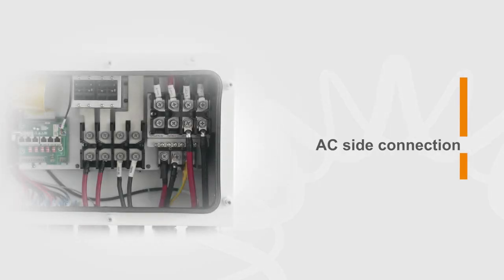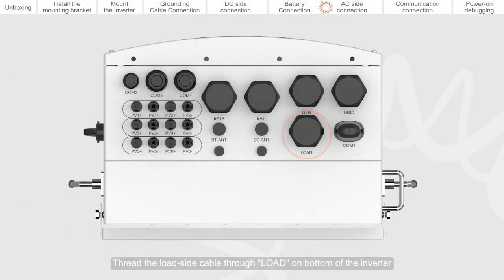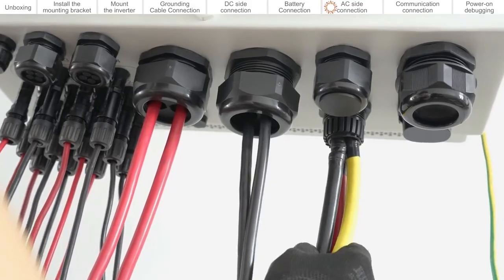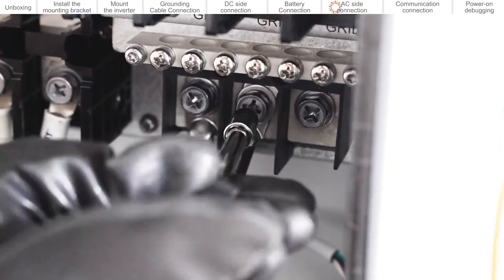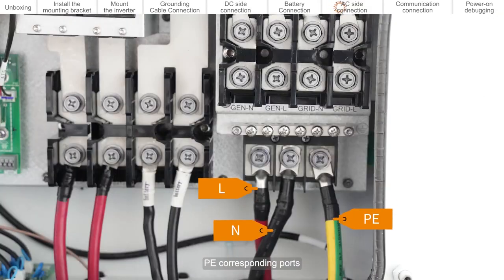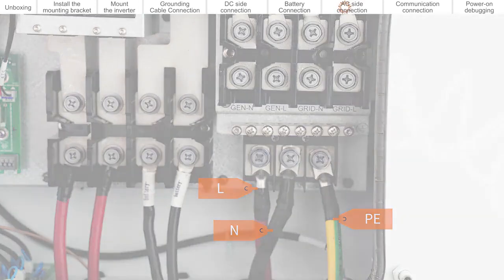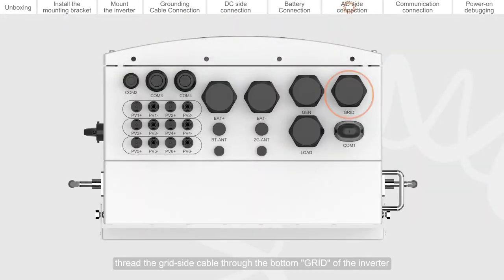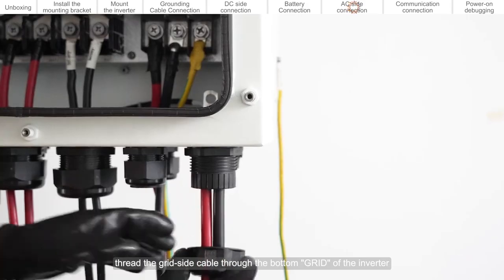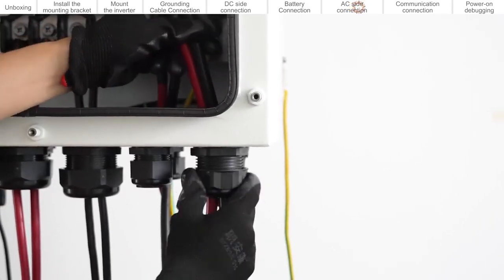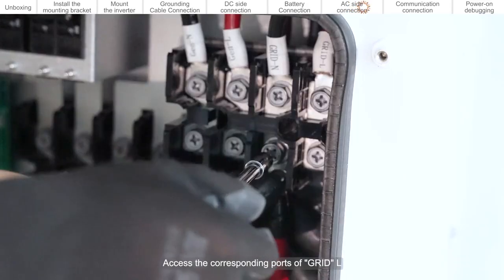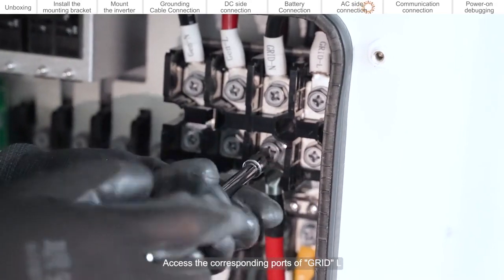AC side connection. Thread the load side cable through the load on the bottom of the inverter. Access the backup L, N, PE corresponding ports. Similarly, thread the grid side cable through the bottom grid of the inverter. Access the corresponding ports of grid L, N.